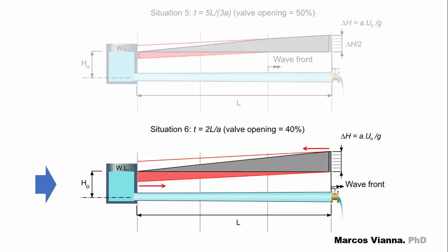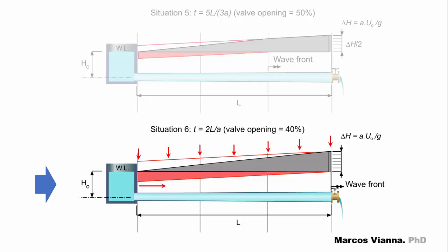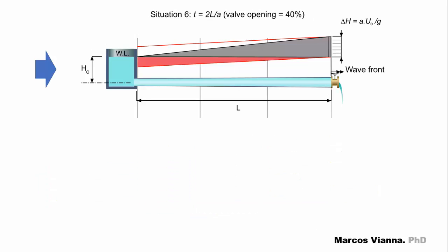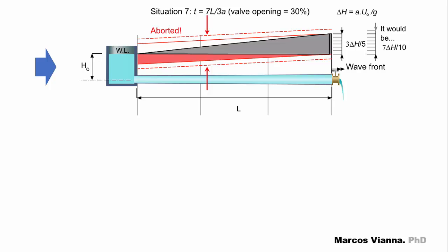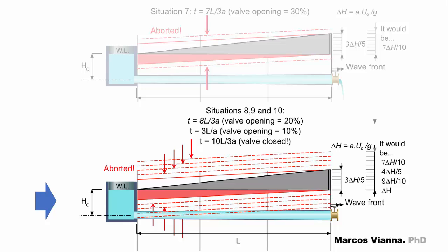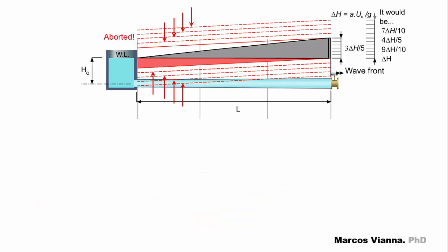2L over A seconds after the beginning of the closure operation, the valve opening is now at 40%. The pressures in the pipeline will be attenuated by the waves reflected by the reservoir along the entire extension of the pipeline. From now on, the pressures will stop increasing in the pipeline — this is the critical situation for maximum pressures. All the pressure waves sent by the valve will be aborted by the waves reflected by the reservoir, and this will happen until the valve is completely closed. In our case, the maximum pressure variation at the valve will be only three-fifths of the value that it would reach in instantaneous or quick closure — which would be equal to AU0 over G, according to Joukowsky.